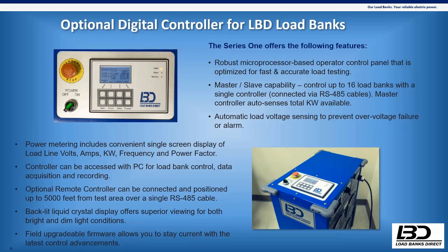Say you want to do a 10 megawatt load test — you don't see it too often, but it definitely happens. You could put four of our 2,500 kW units on the trailer next to each other, run your master-slave cables, and then operate them all from one of these controllers on one of the load banks, running them as one 10 megawatt load bank instead of four separate 2,500 kW load banks. With manual controls, you could still put four units on the trailer, but you'd have to operate each one individually, instead of operating them from one screen and taking one set of readings. So the digital controller definitely simplifies that.